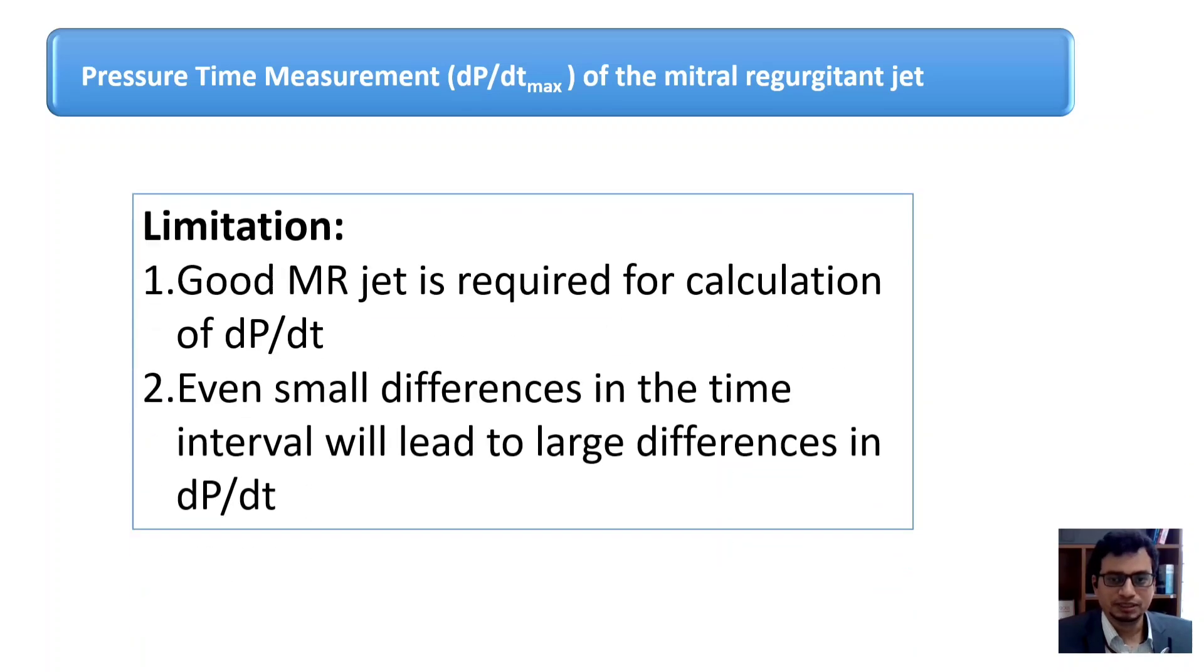Main limitation of this method is that a good MR jet is required for the calculation of DP over DT and even a small difference in the time interval will lead to large change.